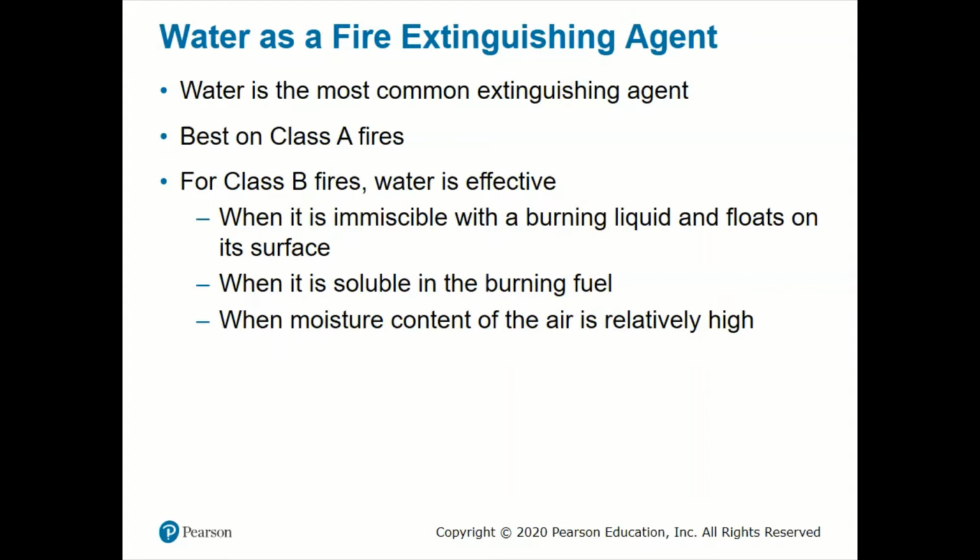First of all, water can be an effective firefighting tool if it is immiscible, meaning it does not dissolve in the burning liquid, and its density is such that it floats on the surface of the substance. Again, that's where we run into a lot of problems. Most of the burning fuels that we're talking about have really low densities. And so water isn't going to float on them. It's more dense. It's going to sink.